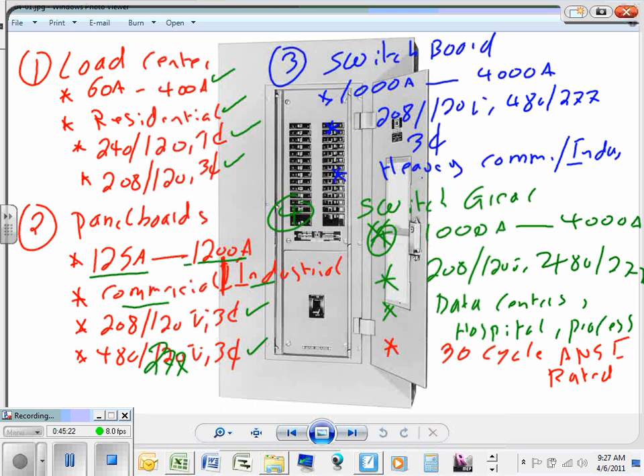So you can use it as a main. What happens is you can use a panel like this as a main, guys, and then a sub panel like receptacle panels. In our project, Brad, all the panels that we're going to have are going to be panel boards. Some of them are going to be 225 amp. Some of them, like the mechanical equipment, when we sized the mechanical equipment, guys, if you remember, we came up close to an 800 amp panel. So we're going to have an 800 amp panel board thrown in the wall with big circuit breakers coming out of it, a panel board.